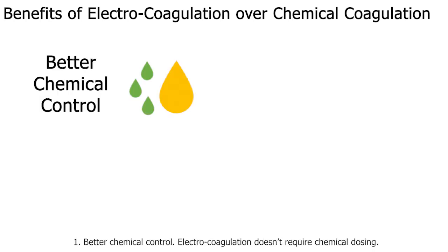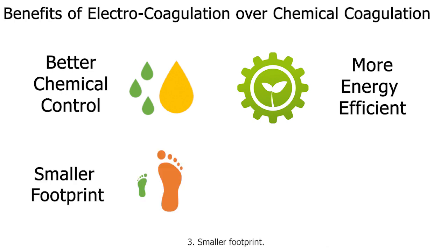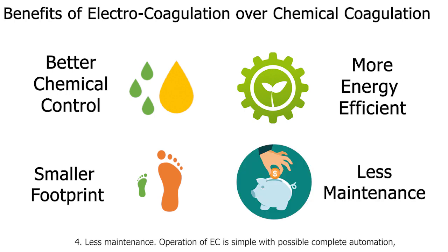Benefits of electrocoagulation over chemical coagulation are being explored. Potential advantages include: one, better chemical control — electrocoagulation doesn't require chemical dosing, minimizing chemical transportation and handling; two, more energy efficient — the energy consumption per coagulant produced by electrocoagulation could be reduced significantly due to the high conductivity of seawater; three, smaller footprint — electrocoagulation reactors are compact as they don't require rapid mixing chambers.